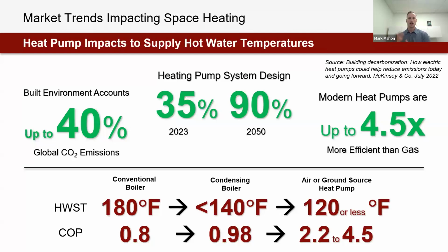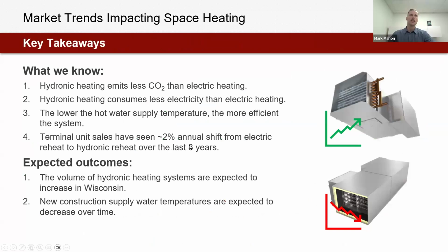We think broadly that we're going to continue to see hot water supply temperatures trend down. The 180-degree system for a hydronic heating system of the past is becoming a 140, is becoming a 120. In some markets it already exists at 115 to 95 degrees. And with that, we get a lift in coefficient of performance for those heating systems. The lower the hot water supply temperature, generally the greater the coefficient of performance as well.